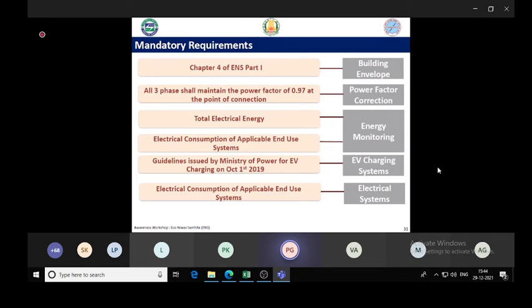So mandatory requirements wise, first of all, part 1, whatever we have seen so far, the RETV, U value, openable window to floor area ratio, all these are mandatory. Then the other mandatory requirements: one is power factor correction. Power factor should be maintained above 0.97. And we need to monitor the energy consumption of end-use systems, like, for example, your common area lighting, common area systems. We need to have sufficient energy monitoring.